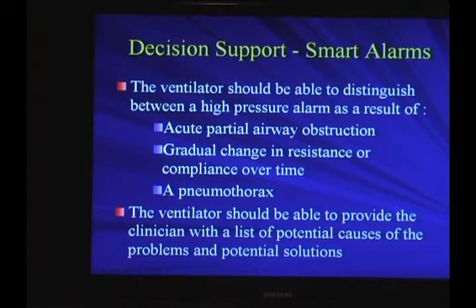But the increase in pressure over a short period of time, 2 breaths, as you all know, that's a pneumothorax, or high probability that's what's a pneumothorax. This is something we need to respond to immediately. And ventilators should be able to identify that. I mean, why do we need to have a persistent alarm just because we hit the high pressure, once on a given breath and require you to come to the bedside to readjust things in order to eliminate that alarm, as is the case with some mechanical ventilators. This, I think, will change because of all the pressure that's being put on manufacturers to do it.